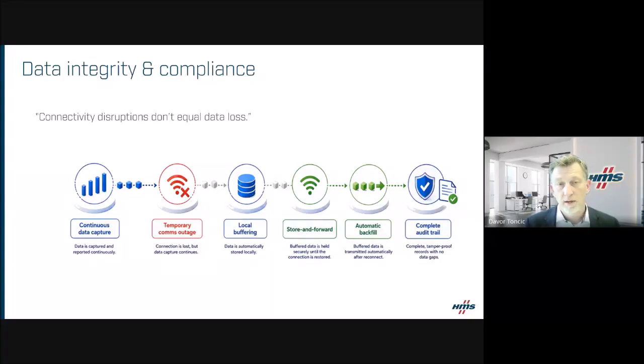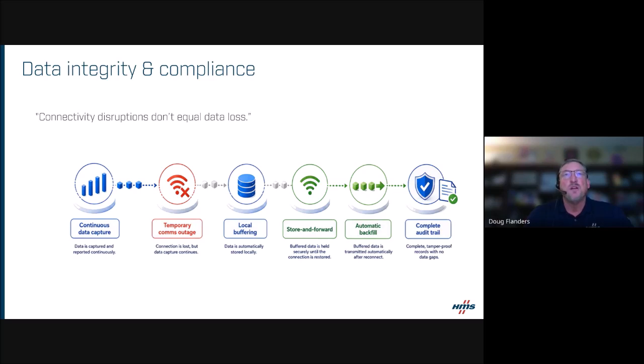That's a really good way of thinking about it - you want to make sure the data on the site you're monitoring is actually being transmitted and collected, for regulatory purposes and also for data integrity. The key is store and forward: you're still collecting the data even if you lose connectivity, storing it locally on the device, maybe in memory or an SD card, and it backfills once connectivity is back up. It's really important to have that type of device and connectivity strategy.